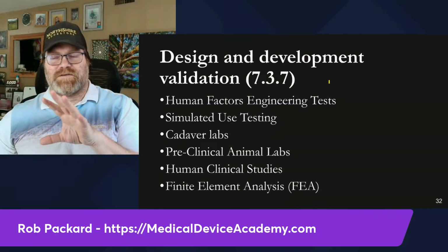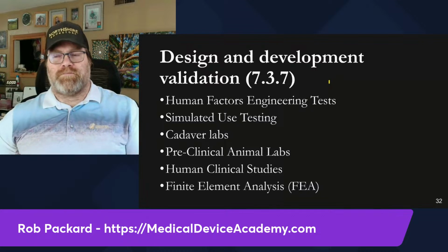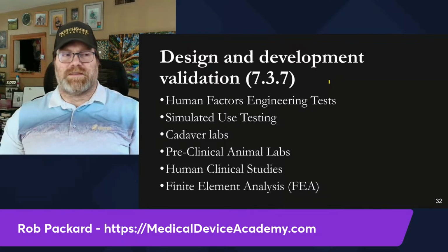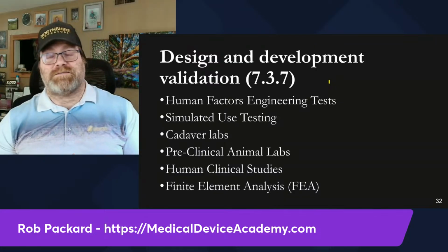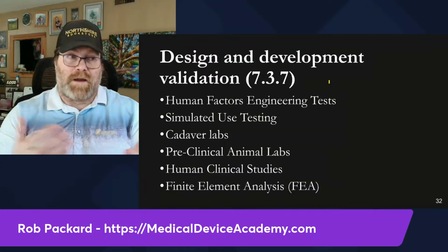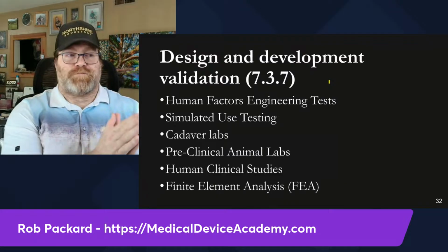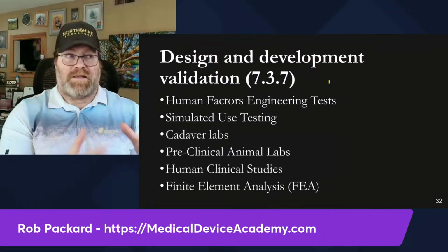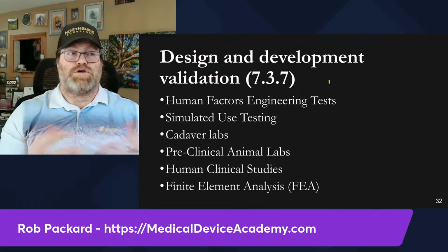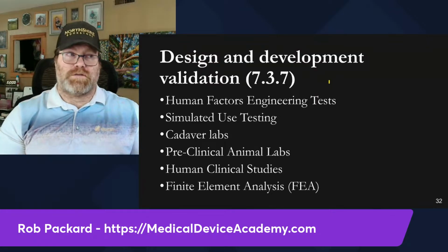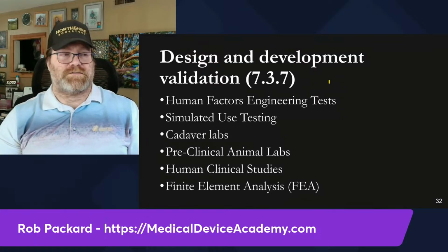Unless you have a very similar device to a previous version that already had usability testing, you're probably going to have to do that. So you're going to have to become an expert in IEC 62366 or hire a firm that is. For simulated use testing, that could be part of the human factors. It could be part of your performance testing. It could be formative testing as well. That's earlier in the phase before design freeze.